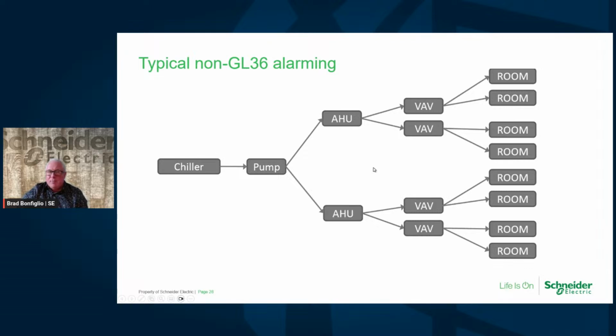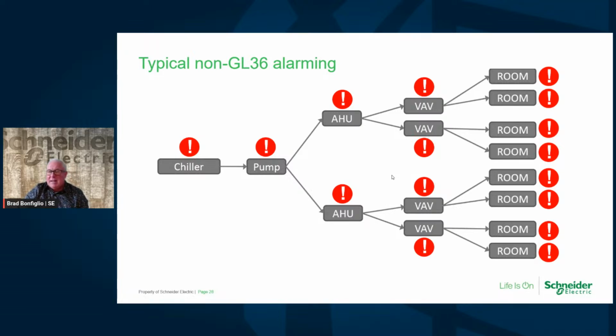Traditionally, if you don't have Guideline 36, and you all know this all too well as facility managers, you get a chiller alarm first. Then you get an air handler alarm shortly after, then the pump alarm, the VAV alarms, and then the room alarms. That's a lot of alarms to figure out what is happening in the space, because all of this comes in at one time, or within several minutes. So you don't know what actually caused the problem. Where was the real issue? When you get too many alarms, what generally happens is you start ignoring them, which is not a good scenario if you're a facility manager, especially if you've got critical alarms coming in, but a whole bunch of other alarms are hiding the real reason for the problem.